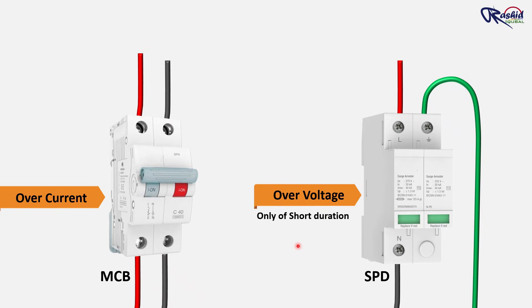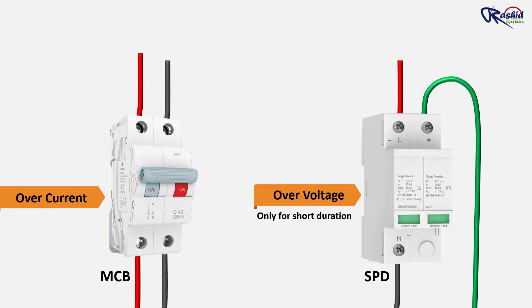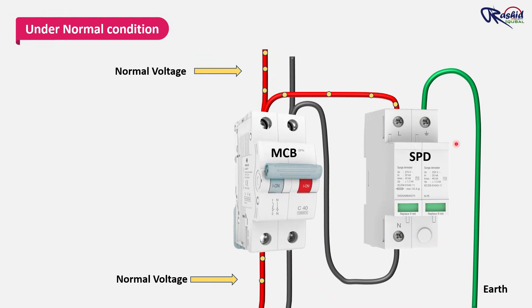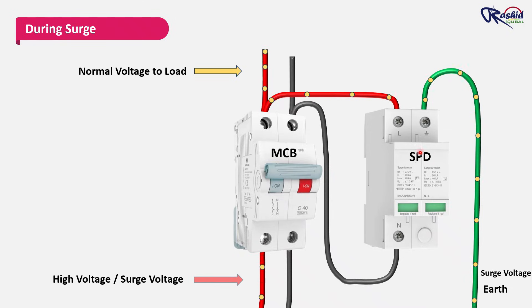So what exactly is an SPD? An SPD, or surge protective device, is a device connected in the electrical system that protects equipment from surges. During normal conditions, power flows smoothly through the electrical circuit without any disturbance. The SPD remains completely inactive, acting like an open switch. All connected equipment receive a clean and stable voltage supply. But when a surge comes, the SPD immediately detects the sudden rise in voltage and creates a safe path to send the extra energy down to earth.